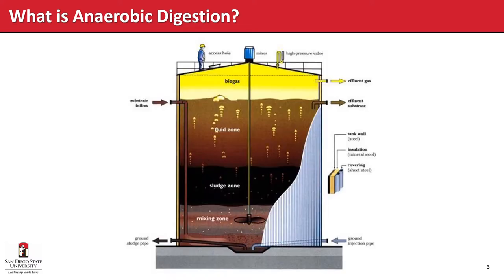What does it look like inside when anaerobic digestion is actually taking place? At the bottom we have the mixing zone where impellers create a well-mixed zone. Above that we see sludge that settles — solids not quite involved in the mixing zone. Above that is a fluid zone with particles but mostly fluid. At the top we have biogas. Substrate comes in at the bottom, gets mixed, produces sludge, and effluent travels up through the fluid zone, while biogas is released to the headspace where it is captured.